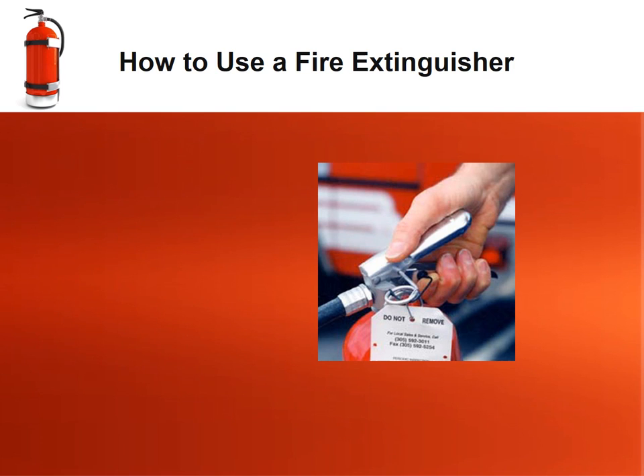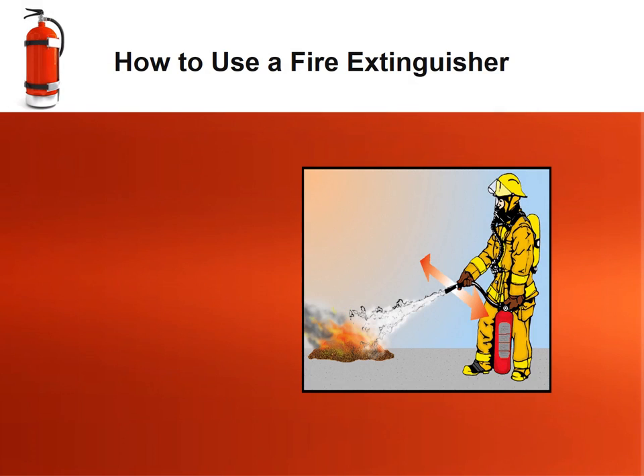Squeeze the top of the handle to open a valve that releases the pressurized extinguishing agent. Then the last S in PASS is sweep from side to side until the fire is completely out. Start from a safe distance of six to eight feet away, then slowly move forward if possible. Once the fire is out, keep an eye on the area in case it reignites.